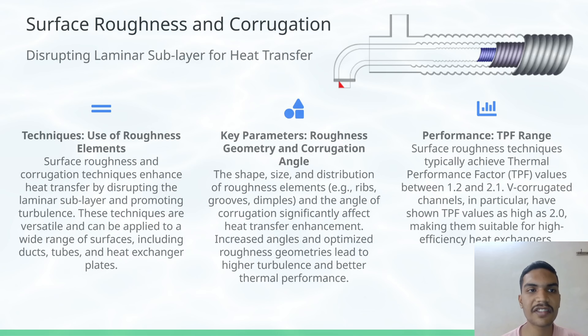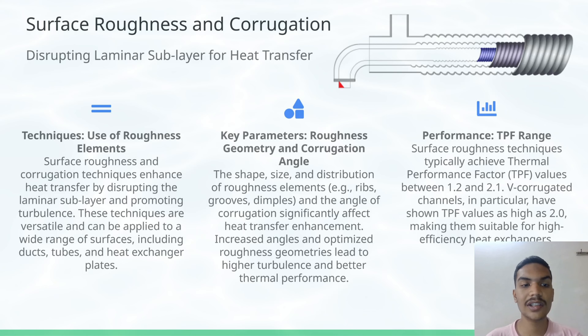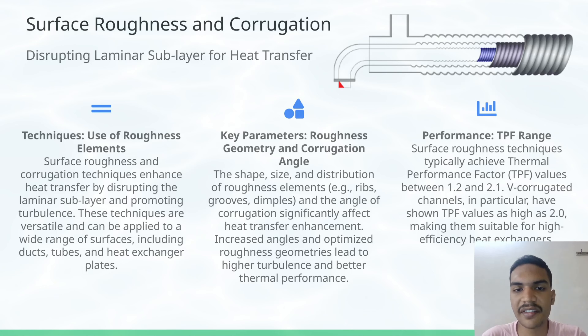The next technique is Surface Roughness and Corrugation. These techniques enhance heat transfer by disrupting the laminar sublayer and promoting turbulence. They can be used for a wide range of surfaces including tubes, ducts, and heat exchanger plates. Key parameters are geometry and corrugation angles.